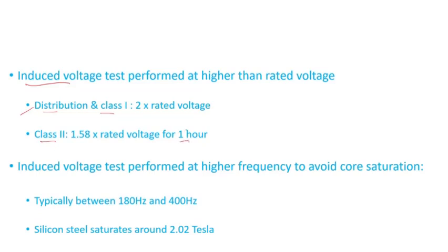For Class II transformers, it's 1.58 times the rated voltage for the one-hour test, and we'll see in other videos—for one minute or a few seconds it can be 1.8 times the rated voltage. But the point that I'm trying to drive here is that the induced voltage test is applied at a voltage that's more than the rated voltage.